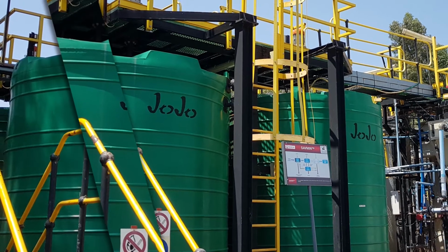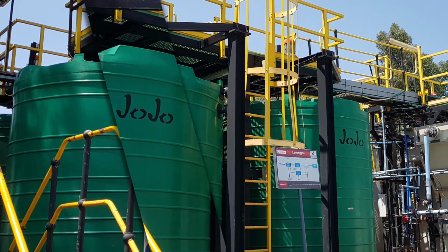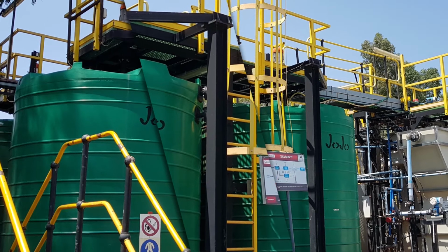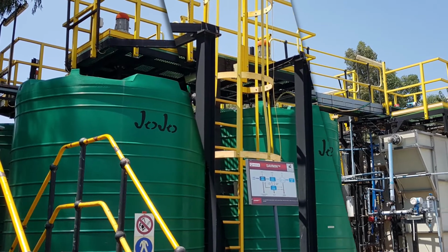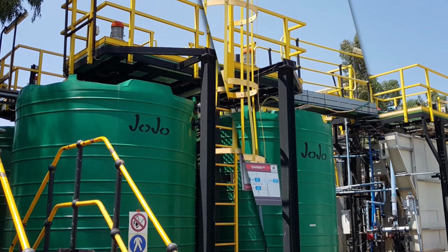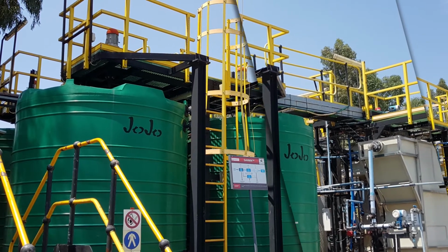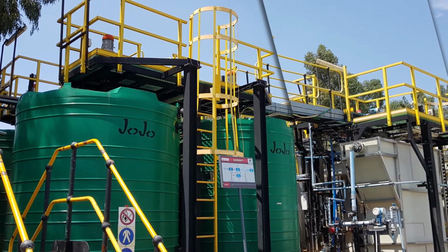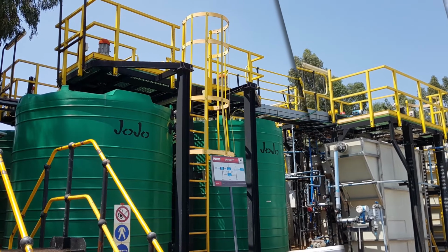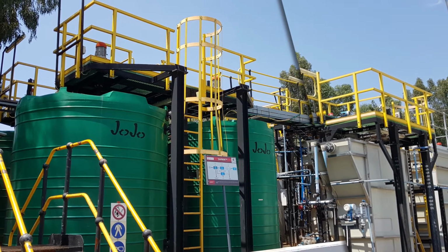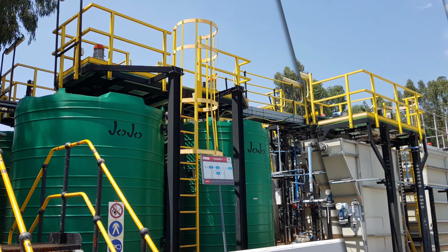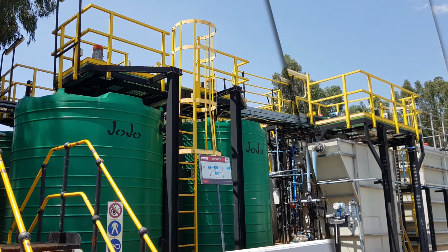The water coming from that stage is then treated with carbon dioxide to lower the pH slightly, because the pH coming from the second stage is too high for human consumption or for discharge. So we lower the pH slightly, and then it also binds some of the dissolved calcium within the water and removes that as calcium carbonate. So the water coming from the carbonation stage is drinking water.